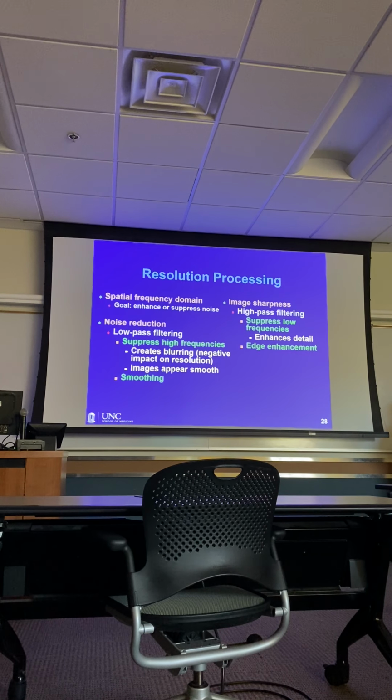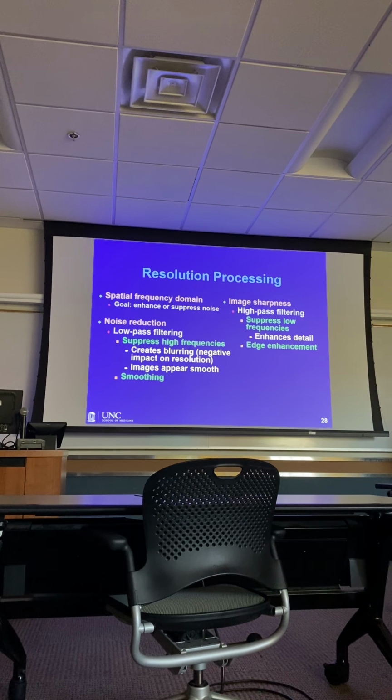But if you're missing data points, you're missing data points. So it really doesn't do anything. It takes away the mottled look, but it doesn't do anything to the spatial resolution. I mean, you should have good spatial resolution if you set everything properly. You know, no motion, your geometric factors were fine. So this actually reduces that spatial resolution, to be honest with you, because it's blurring pixels together. So it really does not help spatial resolution at all. It really just reduces the appearance of the mottle.